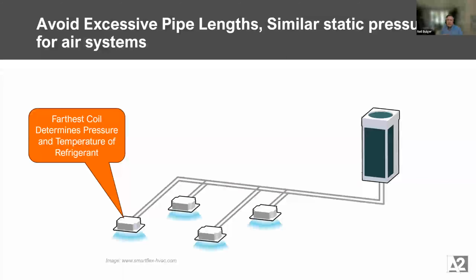You can certainly run VRF pretty far, though the longest pipe length is going to dictate the temperature that system runs at, how hard the compressor works, the pressure needed to push all the way through that pipe. And that's why you'll see VRF distributed around big buildings. They won't just make one central thing that runs very far. So something to be aware of.